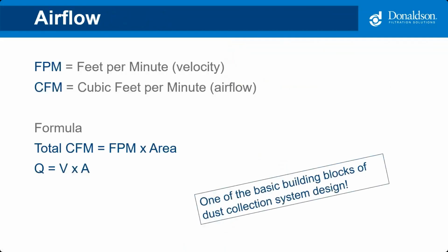There are a lot of different formulas that we use in system design. My algebra teacher would be proud that even after 40 years, I still use algebra. The most basic and widely applied formula I use is for airflow. We refer to it as Q equals V times A, where the Q is the CFM of the air needed. And in order to get that Q, we multiply the velocity of the air, the V, by the area of the hood or duct that the air is flowing through. This formula is one of the basic building blocks of dust collection systems.